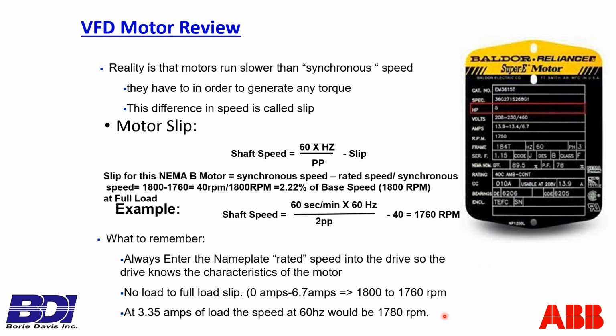Well, what does that mean? That would also mean that motor is not going to run 1760 because it's not fully loaded. That no load to full load slip, that's what that 40 RPM difference means. If this is only half loaded, then that slip's only going to be half of the slip. It'll be 20 RPM, and that motor will be running at 1780. And that's another reason why you need to understand motors don't run at their nameplate.